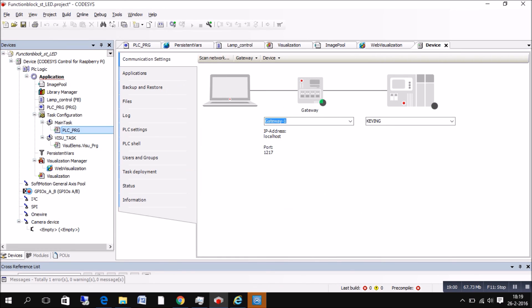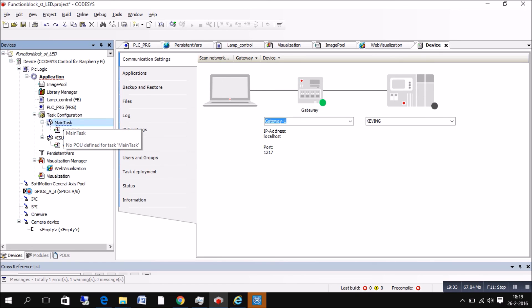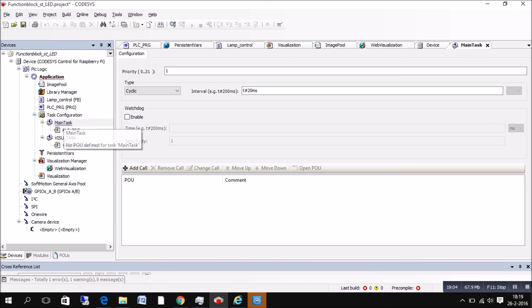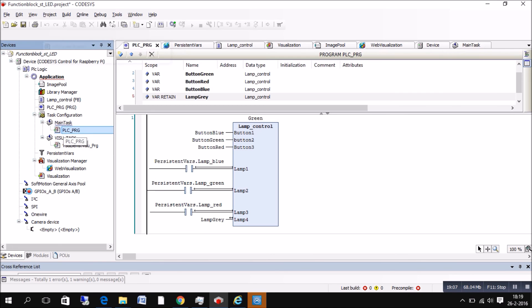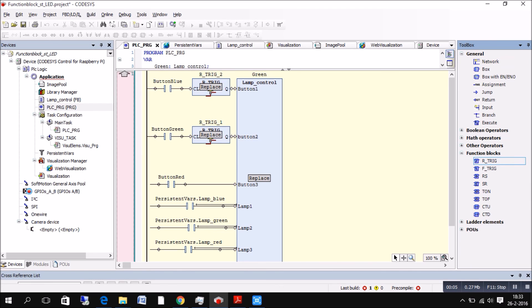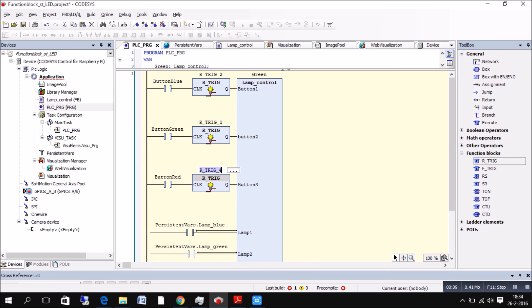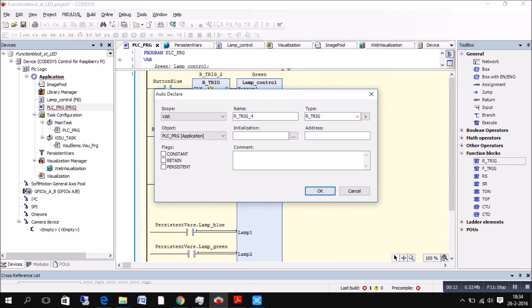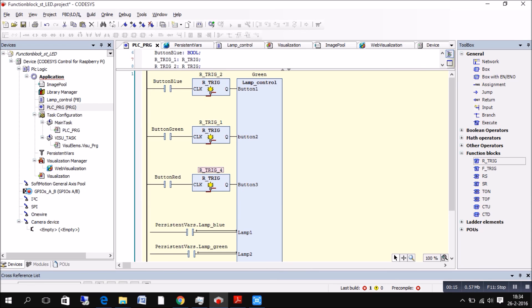There was one thing I forgot to tell you guys with programming because I didn't do that. There is one problem with the program now. That's why you have to put in triggers in between, because otherwise if you press one button, one button press will be longer than one cycle. So it would turn the lamp on, off, on, off, on, off, depends on how much you, how long you hold it. With this, it just creates a pulse. So it will work one time once you push the button. So add those triggers.